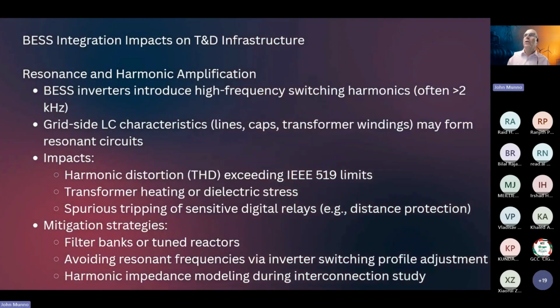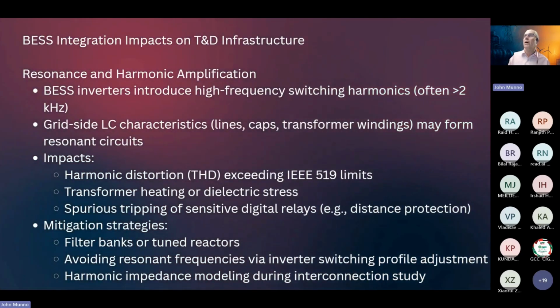Resonance and harmonic amplification. So inverters can introduce high frequency switching harmonics. And this in itself can cause the transformer windings to overheat. When we have resonance in circuits, an example might be if you look at any kind of stringed instrument, musical instrument, a guitar, a harp, a piano, where it vibrates, the vibrations are different depending on the frequency that string is vibrating at. And so if you have electrical wire vibrating based on the electricity going in and out or on and off, then you can have a similar effect. And in a musical instrument, when we have a harmonic, we get an increase in the volume of the output of that instrument. And if that happens to an electrical circuit, we can cause damage.